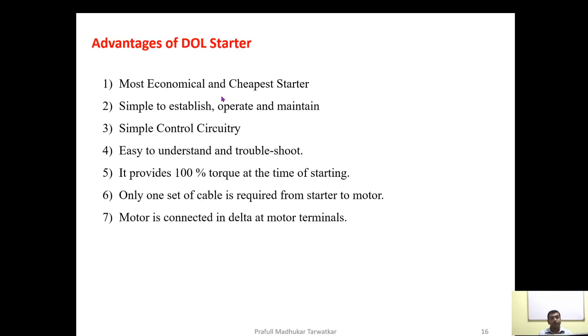Advantages: it is the most economical and cheapest one, simple to establish, connect and operate, control is very easy, it provides 100% torque, and the motor is connected in delta at the motor terminals. It requires only one set of cable for the stator connection.